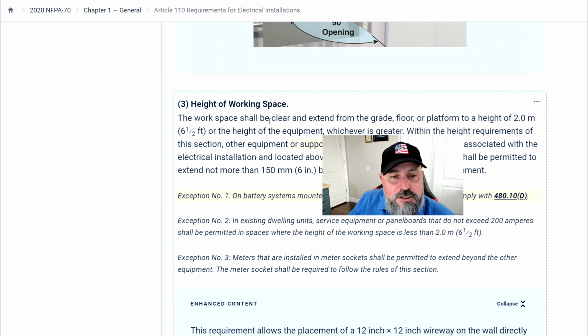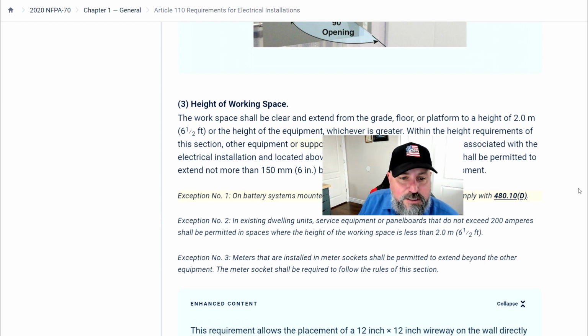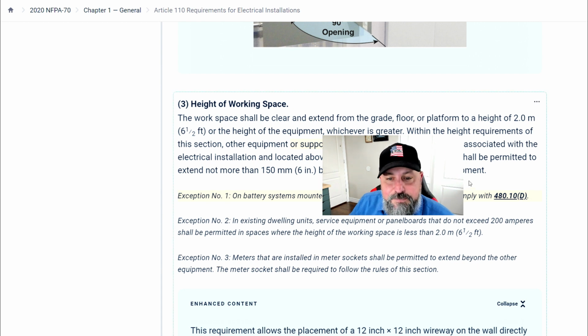The workspace shall be clear and extend from the grade, floor, or platform to a height of 2 meters (6.5 feet), or the height of the equipment, whichever is greater. Within the height requirements of this section, other equipment or supported structures, such as concrete pads associated with the electrical installation and located above or below the electrical equipment, shall be permitted to extend not more than 6 inches beyond the front of the electrical equipment. So concrete pads, support structures, the housekeeping pads that we put in and everything, those can't extend more than 6 inches in front of your equipment.